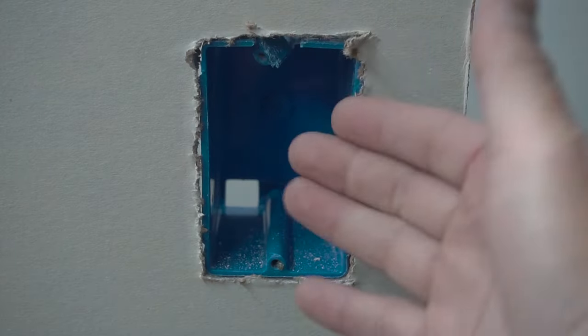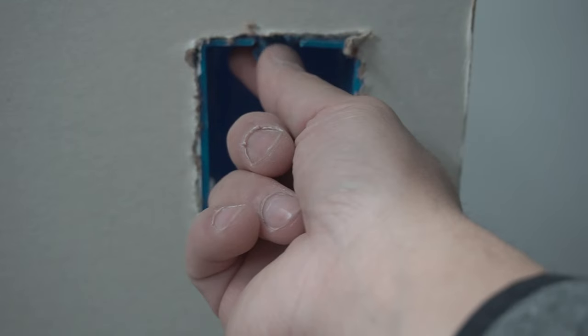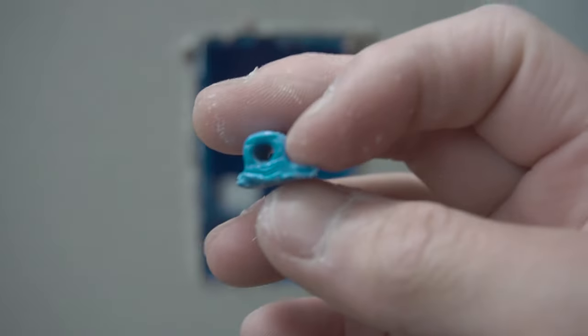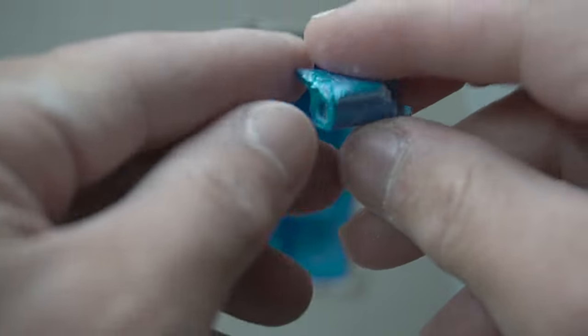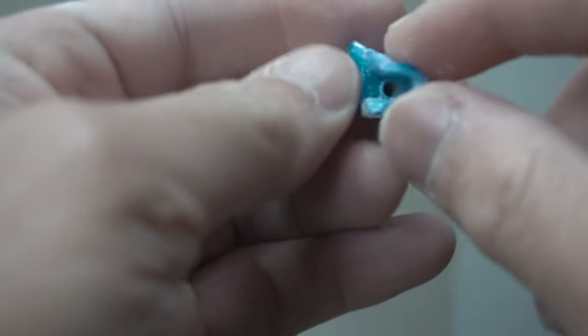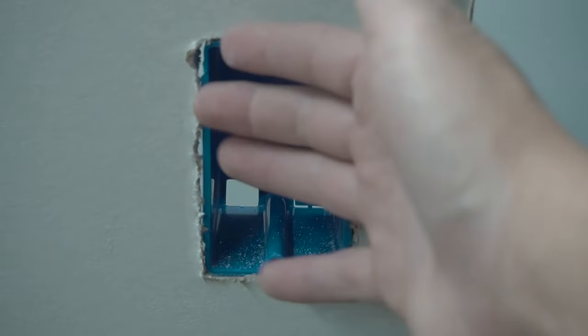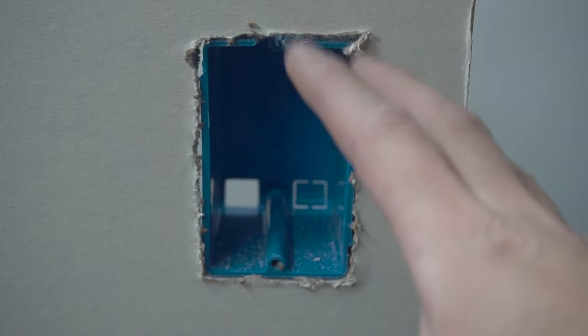This is just a mock-up — that's why I don't have wires running through here. It's for demonstrational purposes only. This part right here is broken off, or maybe it's just hanging on the thread and breaks off like that. This part of the J-Box is what holds the screws in place. It runs into about half an inch of thread until your screws go into nothing. So once this is broken, you might think the J-Box is useless and you'll have to replace it. But before you do that, let's explore some of your options.